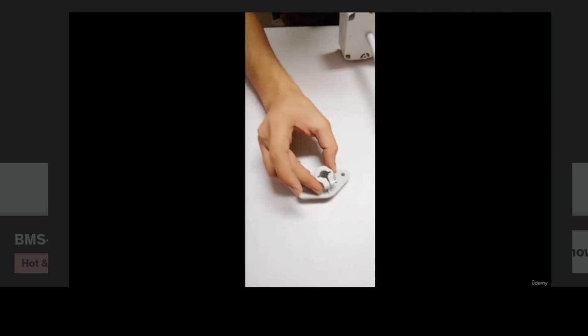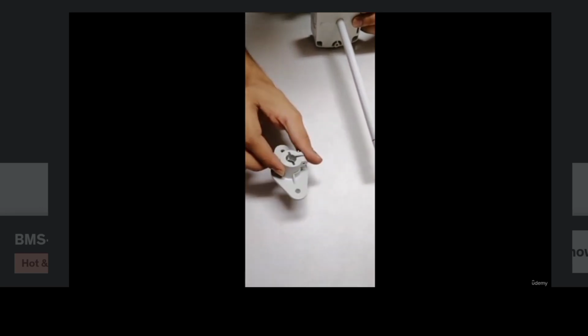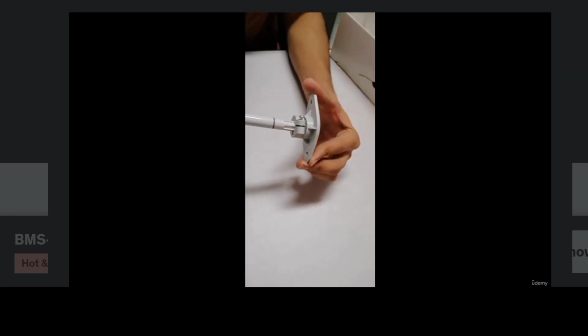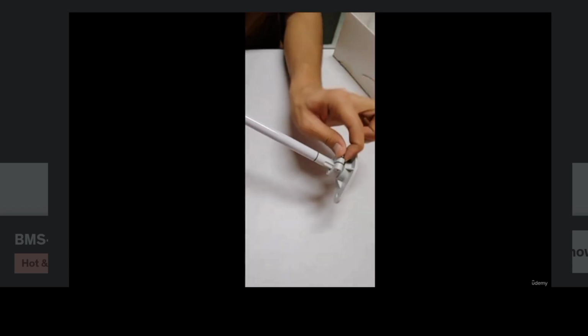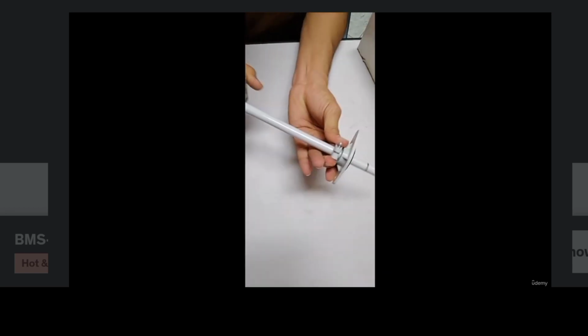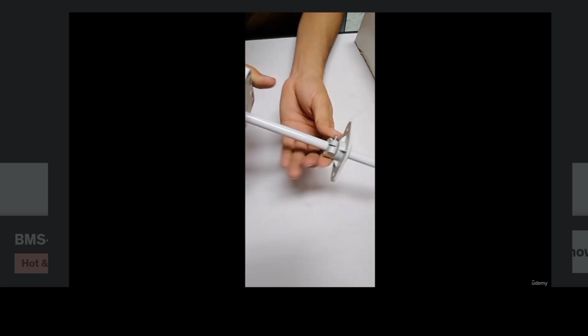This is the probe which goes inside the duct. This is the mounting flange. Here we have an arrow showing the direction of the airflow. So we install this mounting flange on the duct, and then we insert this humidity sensor inside the duct. There is a screw here to loosen. Like this, we can insert this humidity sensor inside the duct.